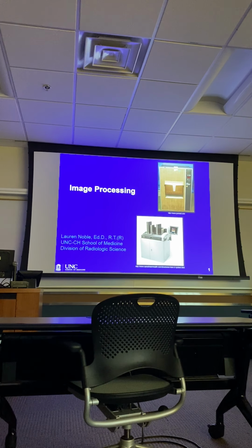Believe it or not, film actually consists of gelatin, just like Jell-O. When it goes into the developer solution, it swells and gets real mushy so the chemistry can get in there to process the image. Then in the fixer tank, it shrinks that gelatin base back, then goes through wash water, then a dryer, and the film comes out here.